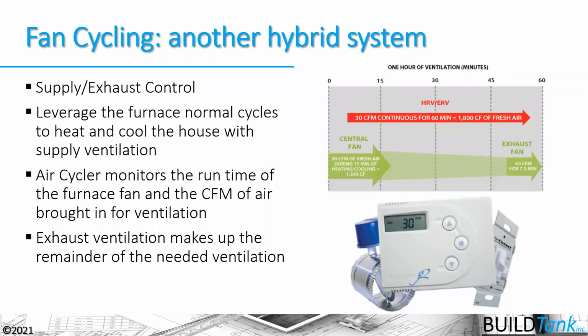Now, here's another example of an exhaust side hybrid system that leverages that duct to the outside. It runs as a supply side ventilation system when the furnace is running. And then when the furnace isn't running, it runs as an exhaust side ventilation system here. So you're kind of getting the best of both worlds from a supply and exhaust ventilation strategy in this type of system.